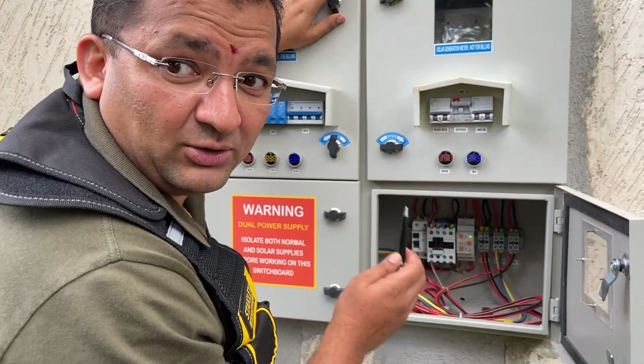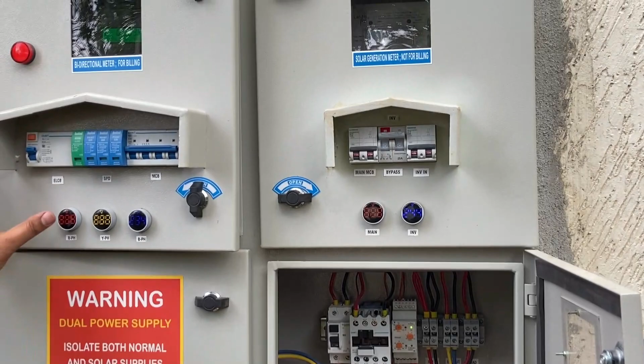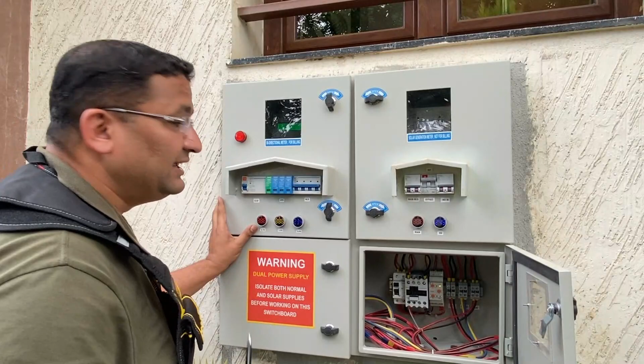We also have an over voltage and under voltage protection relay. Before the power gets into the inverter, again we have a stabilizer on the top. So before the power gets into the inverter, it goes through one ELCB, over voltage and under voltage protection relay. Then it goes into the stabilizer and so on, which we will see now. So this is about the first part of the incoming wiring from the grid.